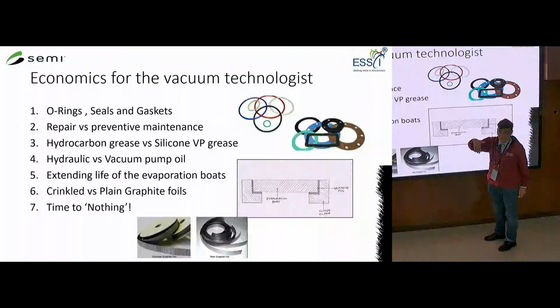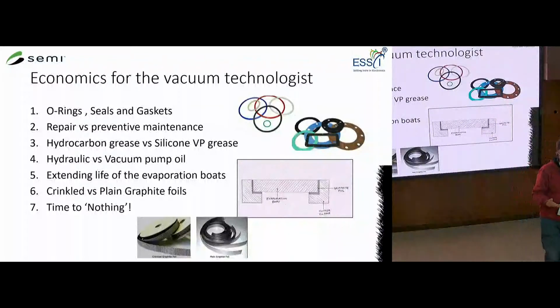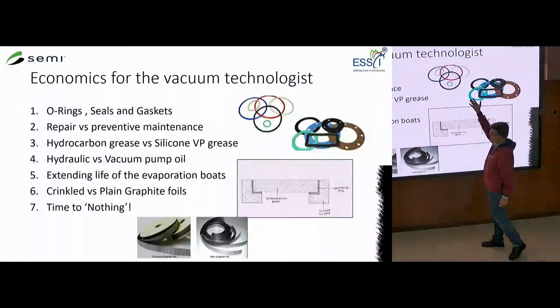If you're going to UHV, ultra high vacuums, you actually need to make sure that these are appropriate components. You will not normally use just normal polymer seals that are available in the market. These seals will degas. They would have some atmospheric gases absorbed in them. If you actually use them in your vacuum system, they will outgas, and therefore your vacuum will never be perfect. Especially if you're going to UHVs, you have to make sure that you're using the right O-rings, seals and gaskets. So this is tip 1.